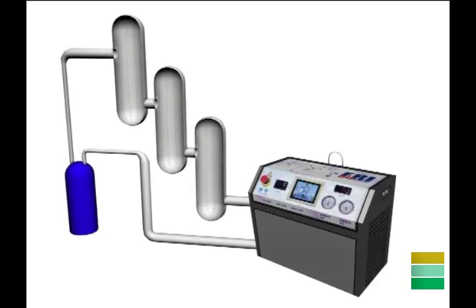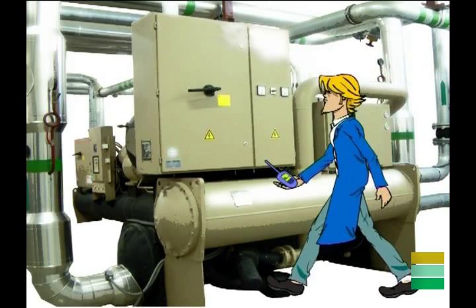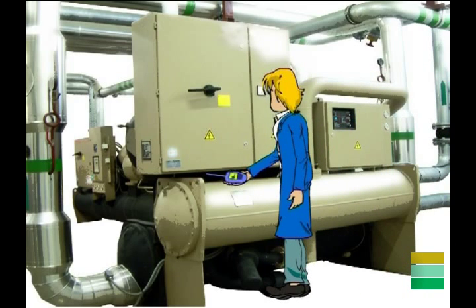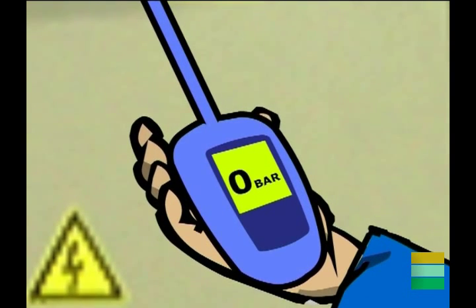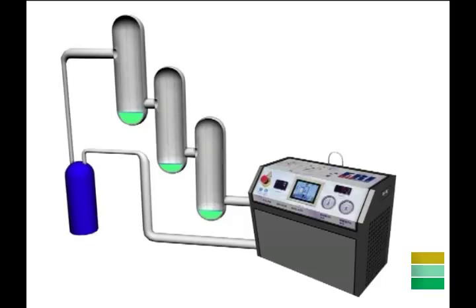Nevertheless, there are several reasons why a single refrigerant is generally used for system cleaning, regardless of whether the one used in the installation could be used. When a system has lost its refrigerant through a leak, we will not be able to use that refrigerant for cleaning. If the circuit has a lower than necessary refrigerant charge, it is possible that the installation, even without a leak, does not have enough refrigerant to exit through its lowest connection in liquid phase.